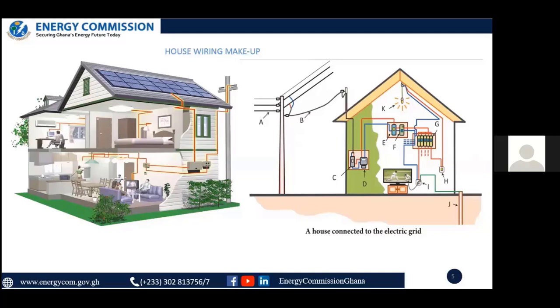But lately there are new developments. ECG and NEDCo, our main power distributors or utilities in Ghana, due to reasons like power theft, have derived means of installing their meters on poles. In this case, coming from your LV lines - phase 1, phase 2, phase 3 - they don't pass through the cutouts before going to the meter. It passes through the meter, then goes to the cutout, since there's already protection in the meter. That's how they're able to do it this way. When it happens this way and you're using the power, we term it that you're now on the grid. Everything has to conform to certain standards and have certain protection before the connection is done. Once those things aren't met, you're breaching the electrical wiring regulation, which the Energy Commission and everyone wouldn't be happy with.